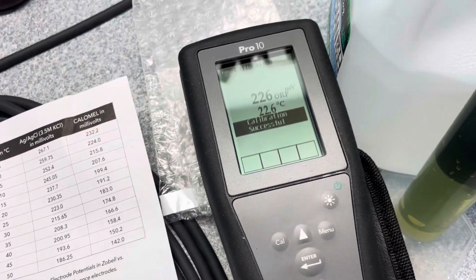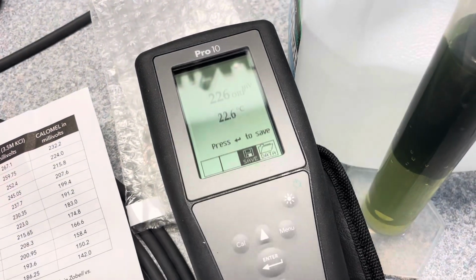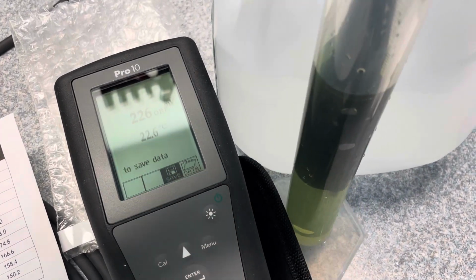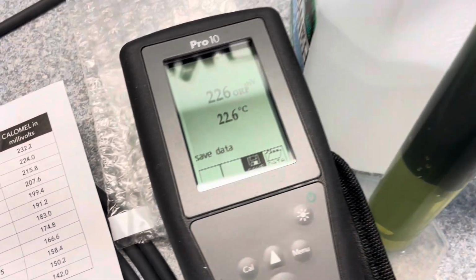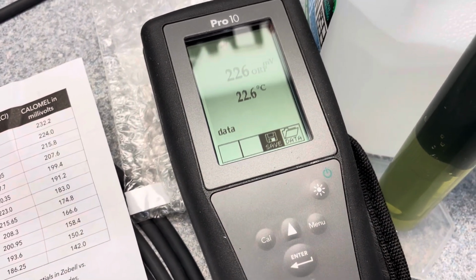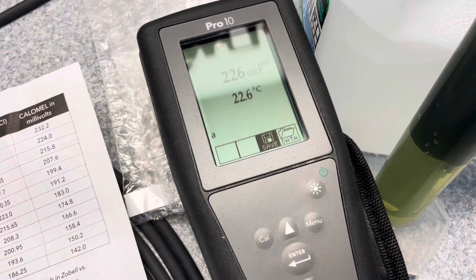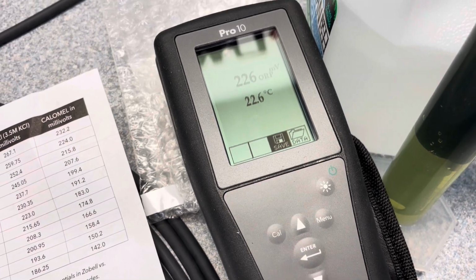Calibration successful. And if you want to verify you have a good calibration, want to make sure it's stable, you can even take it out of the solution and put it back in the solution, let it equilibrate, and you'll come right back to your initial calibration value.